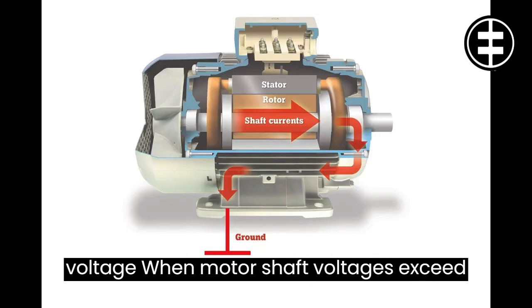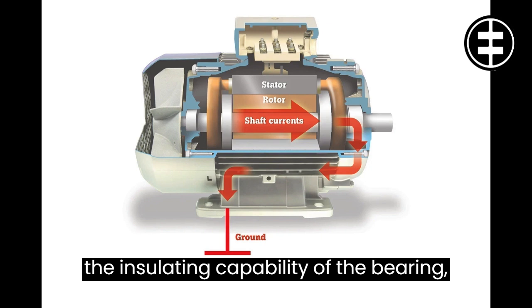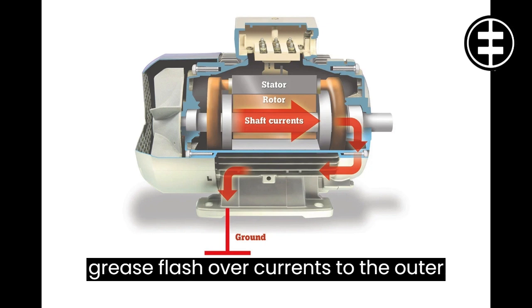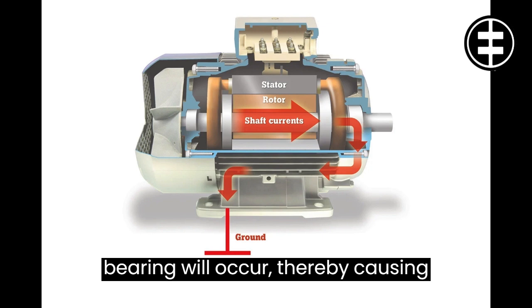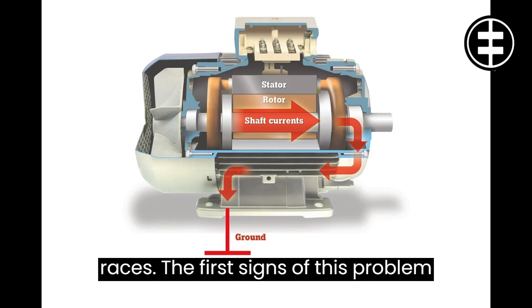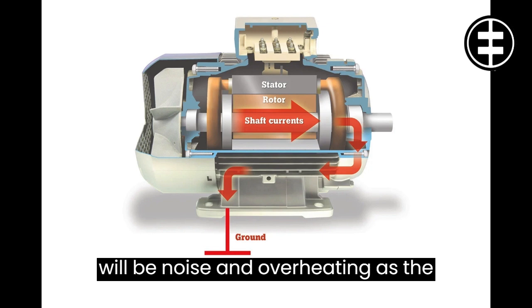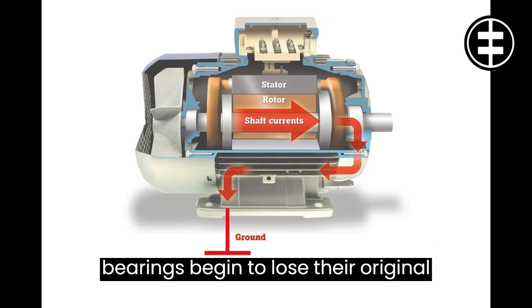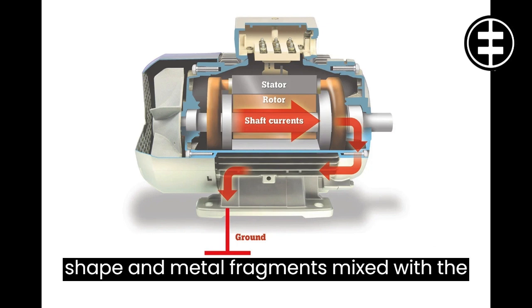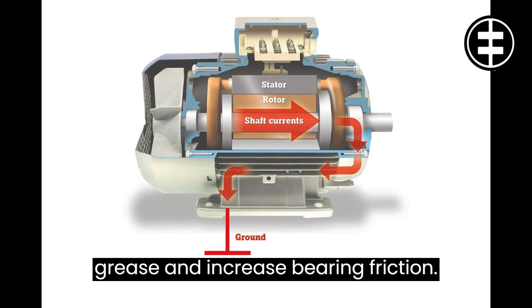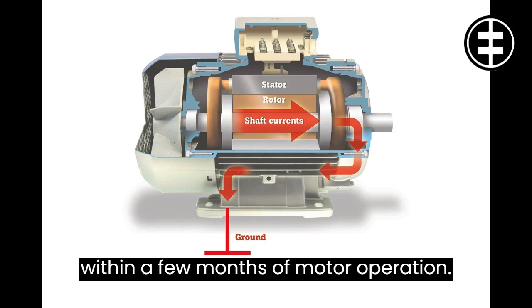13. Shaft voltage. When motor shaft voltages exceed the insulating capability of the bearing grease, flashover currents to the outer bearing will occur, thereby causing pitting and grooving to the bearing races. The first signs of this problem will be noise and overheating as the bearings begin to lose their original shape and metal fragments mix with the grease and increase bearing friction. This can lead to bearing destruction within a few months of motor operation.